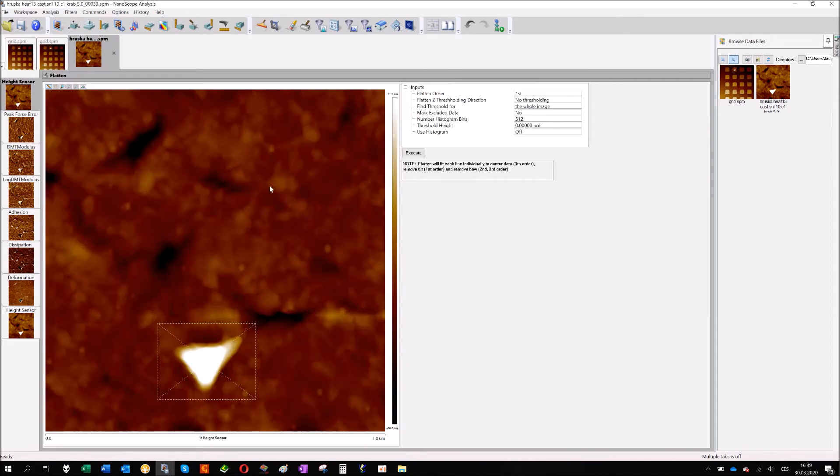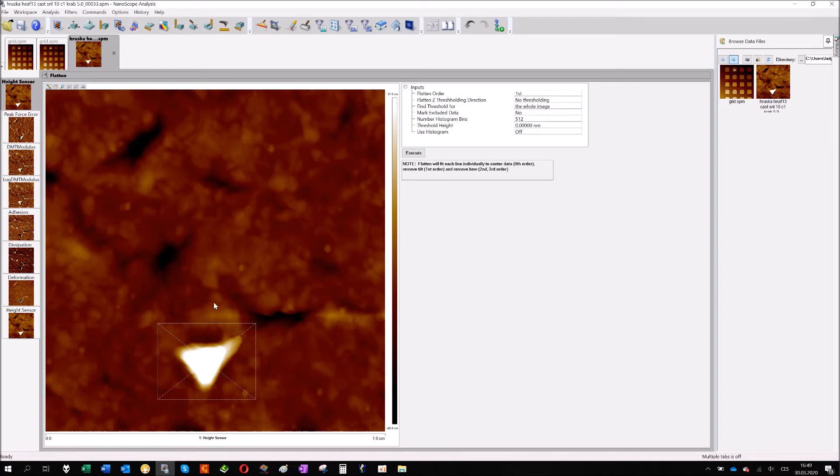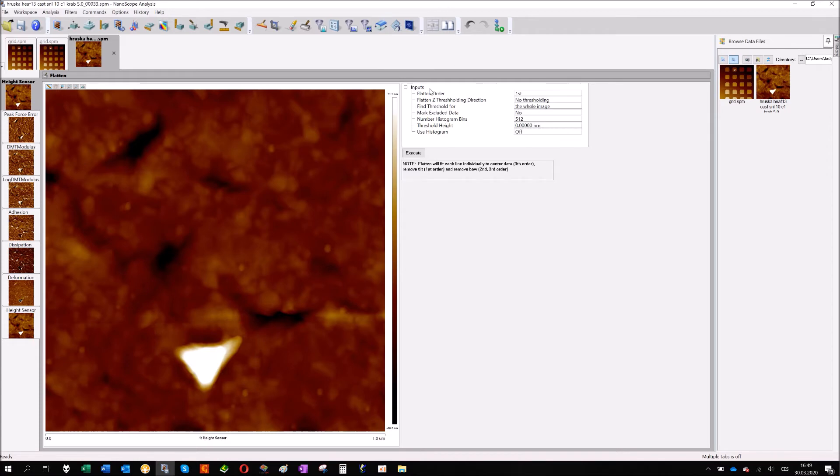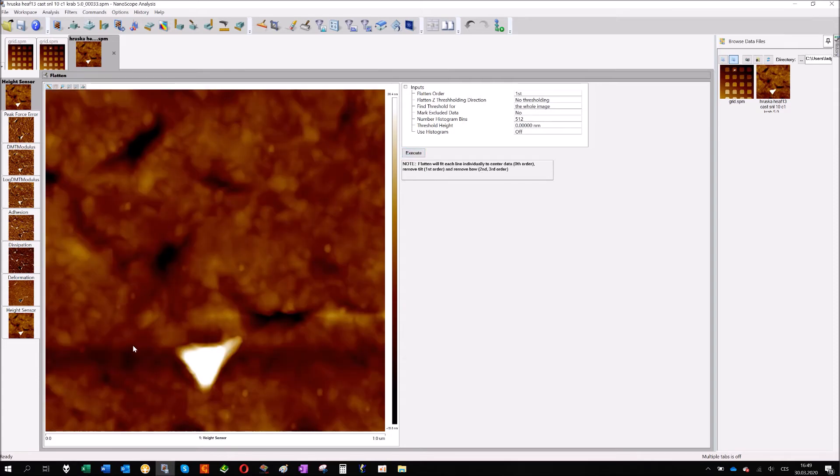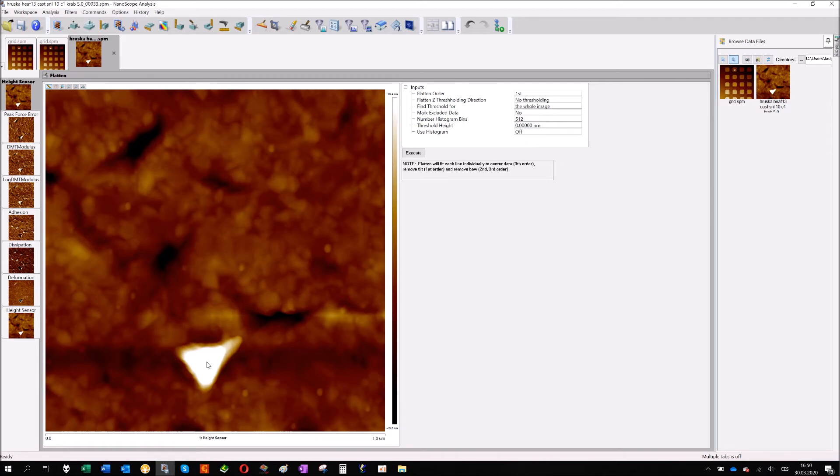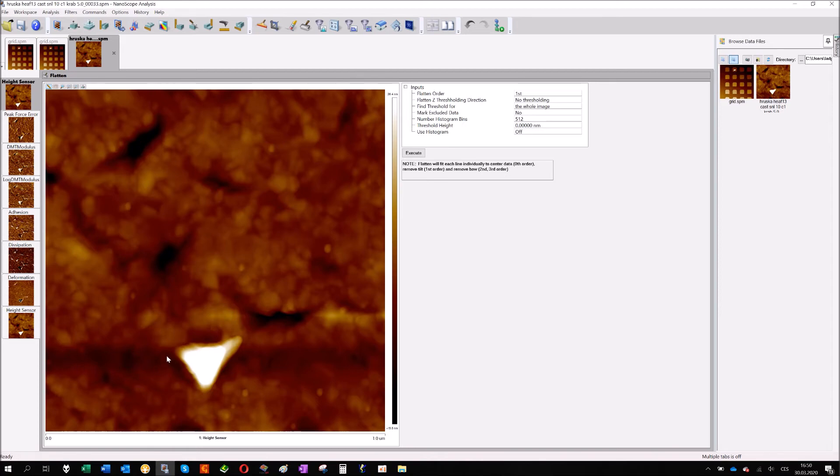This is the sample from the Institute of Physics, Czech Academy of Science. The image looks nice. If I will just do the flattening, just click execute, you can see that it works well here in this region, but here is a very high feature which means that the average for each line is much higher. So you have a bright area which is very high and the dark area here. This is one of the typical post analysis issues when you are doing a flattening, when you are removing the tilt.